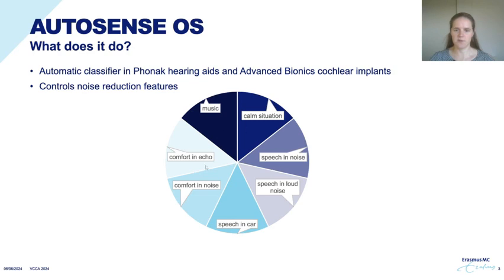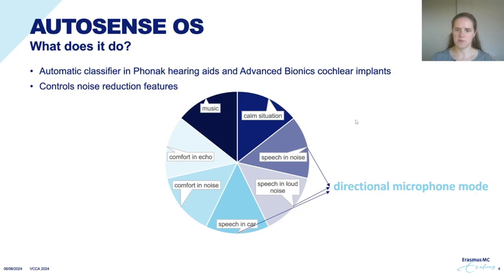It detects the acoustic features of the environment and based on that it classifies the environment into one of the categories listed here. These different categories control the noise reduction features of the hearing devices, and in the case of hearing aids they can also make slight adjustments to the gain settings. One of the noise reduction features controlled by AutoSense is the directional microphone mode, which is switched on when speech is detected in these three categories.